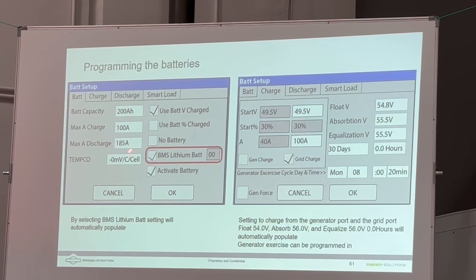And the same on the discharge rate. So the batteries are capable of doing up to 272 amps. And the batteries are going to be sending to the inverter, discharge me at 272 amps, but if you put a lower value in here, it will take the lower of the two values. So you can override the batteries if you want to. And that's how you do it with the charge and discharge rate here.